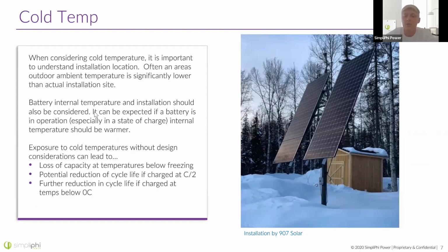What matters is the internal temperature of the actual battery. So if it's 20 degrees Fahrenheit outside and your batteries are encased in a partially insulated shed, and beyond that maybe in a cabinet, all those layers of insulation keep the battery warm. In addition, the battery itself has a large thermal mass, so as it gets cold outside, it maintains its heat for quite some time.